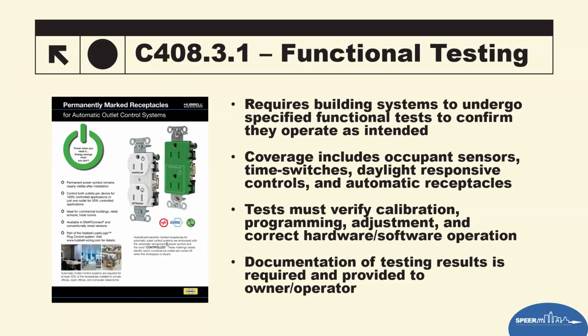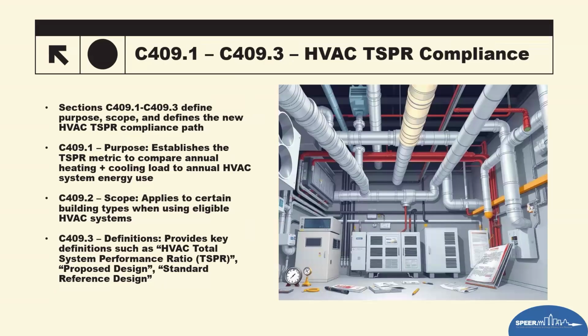So that's going to make sure that, I've not done one like this. I don't know how hard that's going to be, but if you have an occupant sensor, that's easy to do. But if you have a daylight control, it's got to reduce its power by a certain amount when daylight's strong enough outside. So somehow those will have to be tested, either in an override system setup or by other means, but it needs to be shown that it's being commissioned.